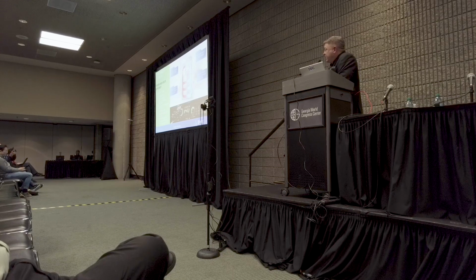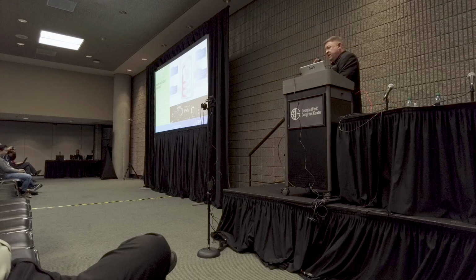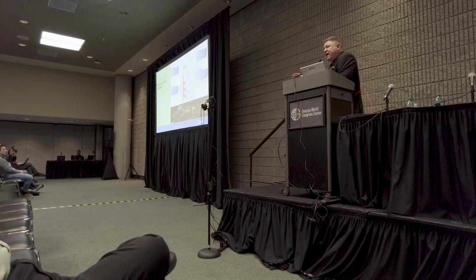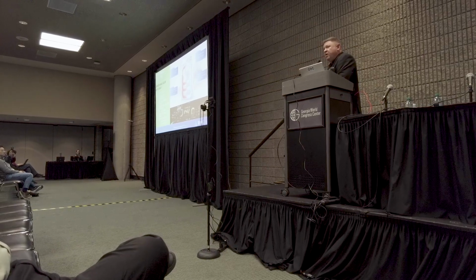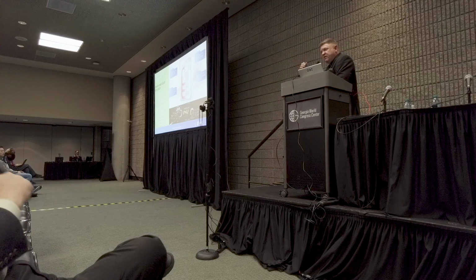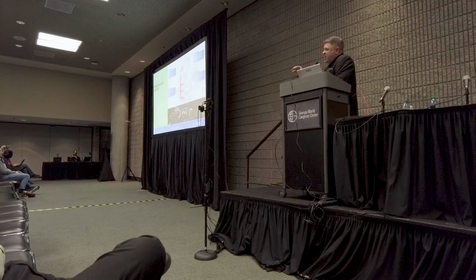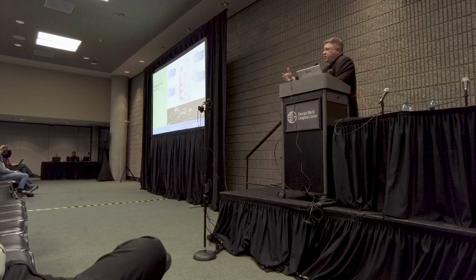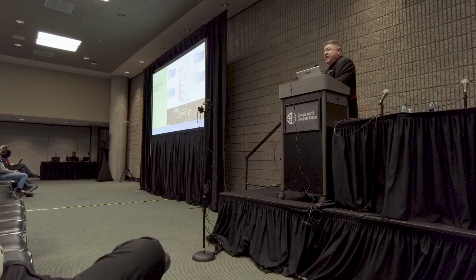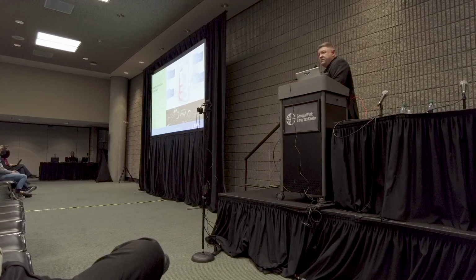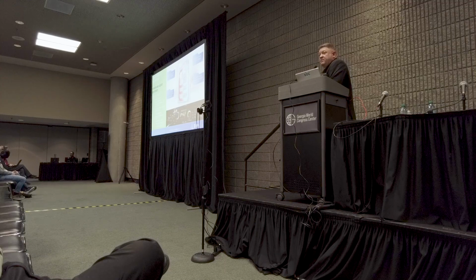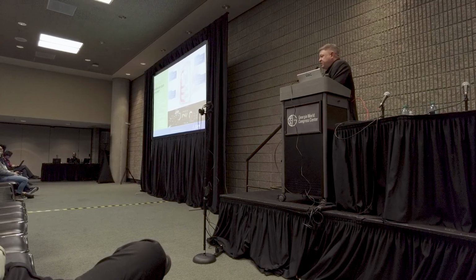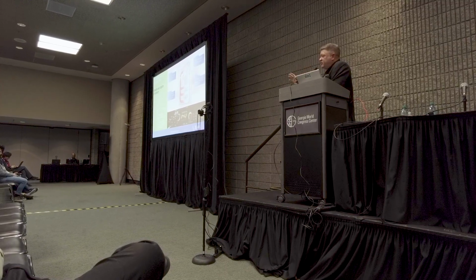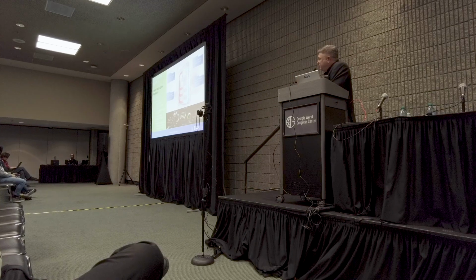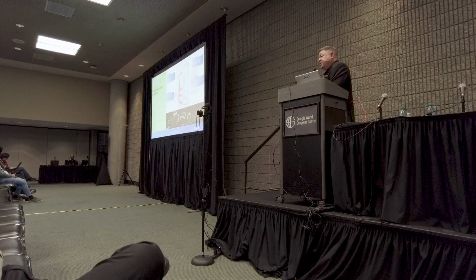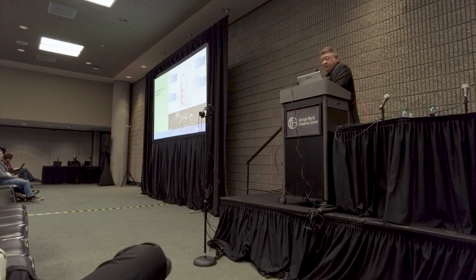In our cabinet design, we use air as the medium inside the enclosed IT cabinet to cool the infrastructure, while above it sits a liquid-air heat exchanger—a very efficient way of moving heat. The exchange happens very close to the actual heat production, and everything stays within the cabinet environment. It's a NEMA 3 sealed cabinet, so no air ever leaves—meaning it doesn't bleed out into the data center itself. The noise from the GPUs and other components stays inside the cabinet, giving you a very effective and efficient exchange of heat at the cabinet level.